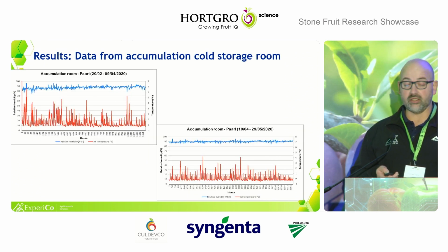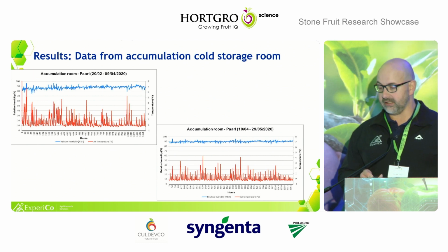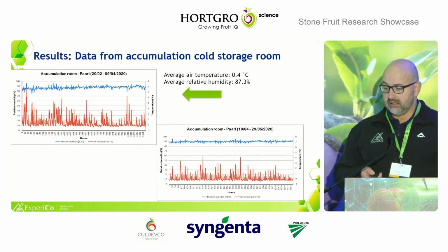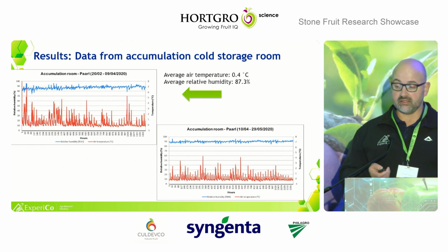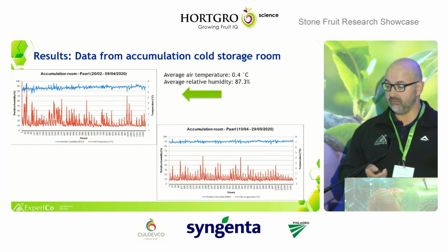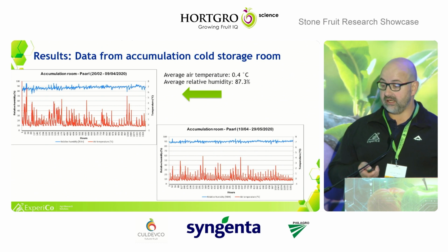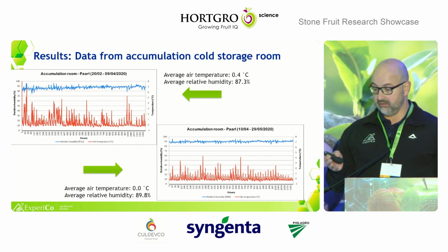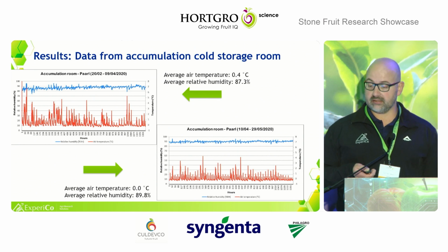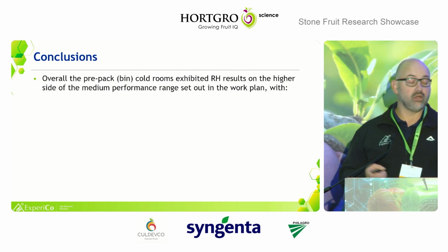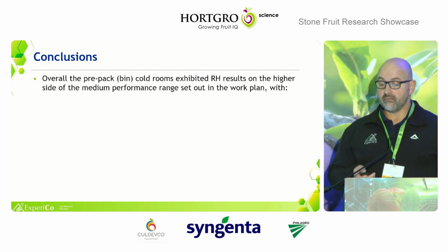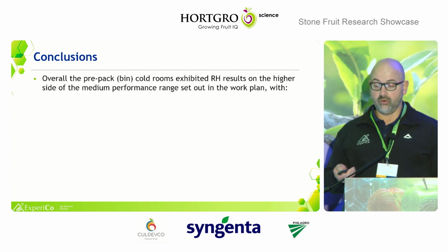So we also looked at accumulation rooms, that's after the fruit has been packed, in the Paarl area. There you can see it's at 0.4 degrees with 87.3% relative humidity, and there was another room that ran at 0 degrees Celsius at 89.8%. That's actually not bad. But the overall conclusion was that the pre-packed cold rooms exhibit relative humidity results on the higher side of the medium performance range.